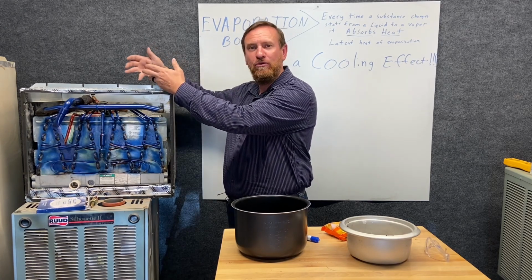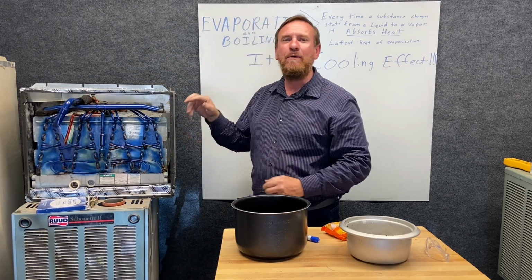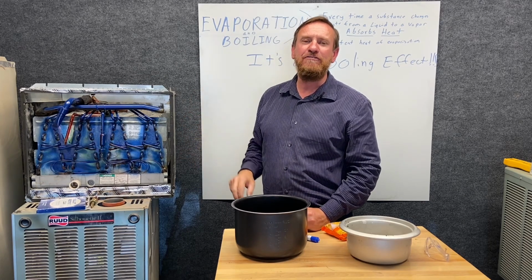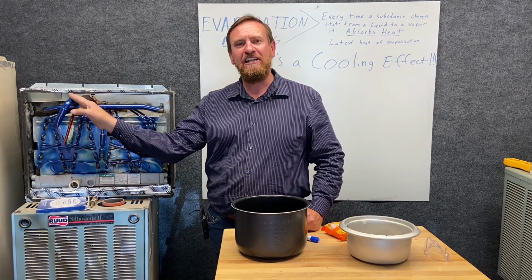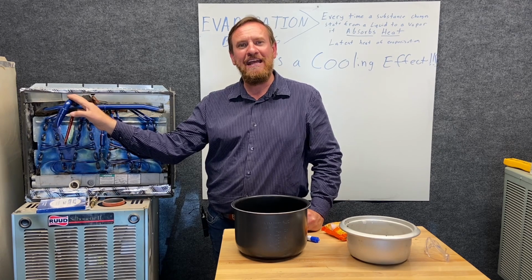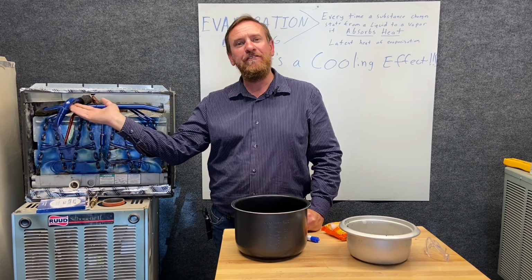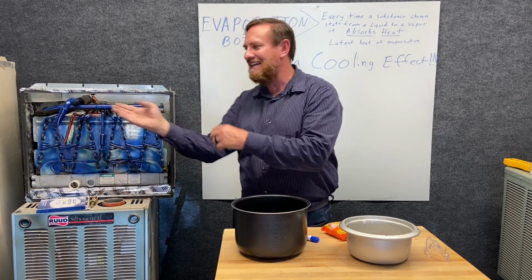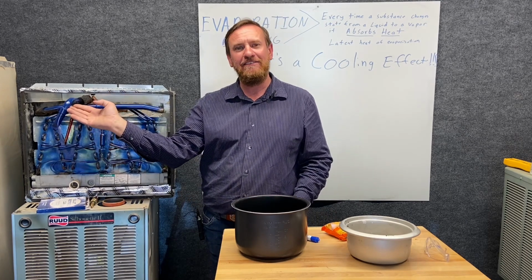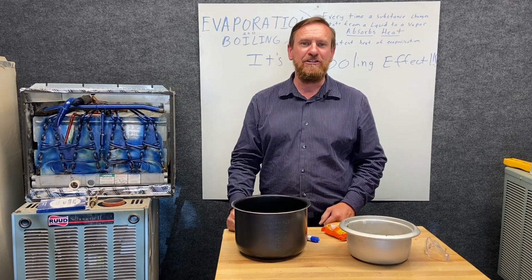So the air temperature comes out cooler. Where did the heat go? It went into the refrigerant. The refrigerant is changing state. We talked about this suction line being a vapor line or a gas line, because now that it's in a full vapor state, all the heat is in that refrigerant as a vapor, but it's still low pressure, low temperature.